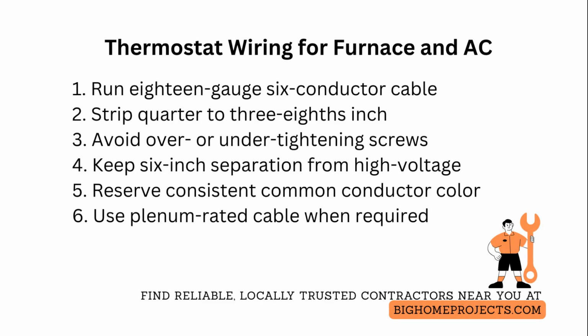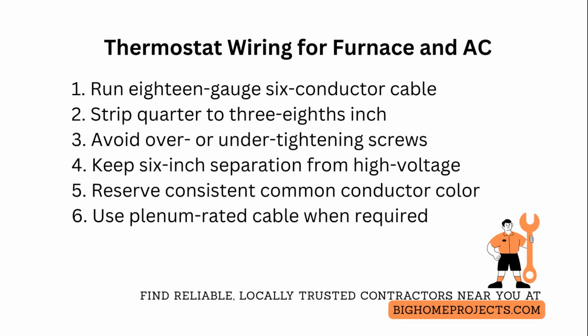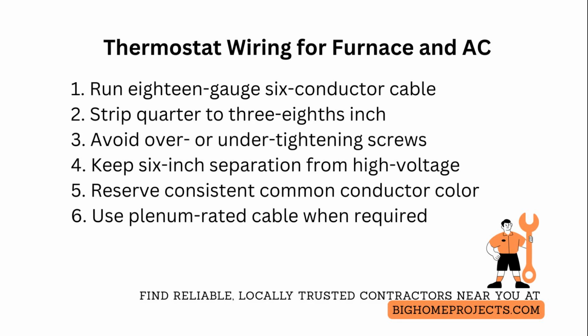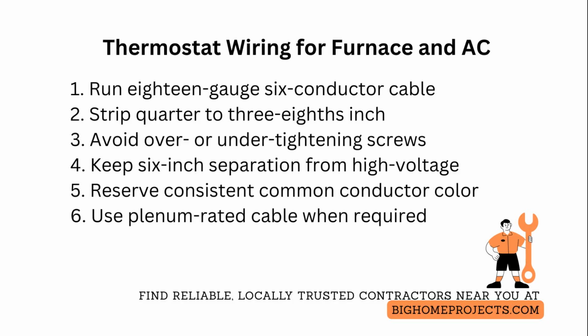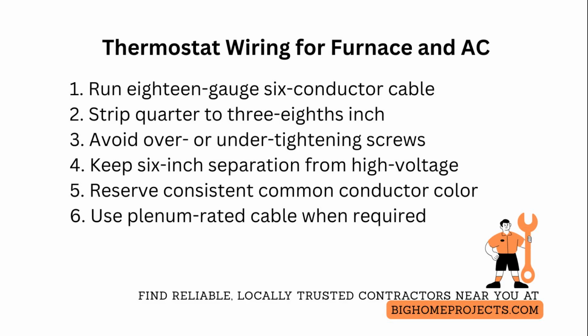This gives you dedicated wires for common, heat, cool, fan, and 2 extra for accessories like 2-stage compressors or smart thermostats that need power and sensors. Strip precisely 1/4 inch to 3/8 inch of insulation from each conductor. Twist and tin the ends only if the terminal screws require it, and avoid under or over-tightening screws, which can cause intermittent connections or broken conductors.